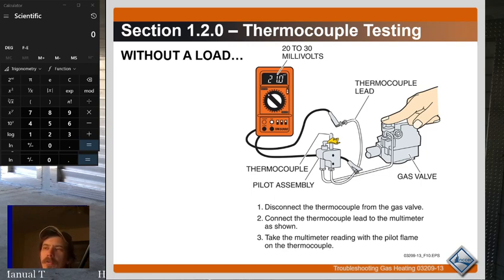And how a thermocouple works is it's a bimetal, two dissimilar metals inside a rod, right? And when it's heated up by the flame, those two dissimilar metals produce a voltage, all right? A millivolt voltage through it, and that is what holds the gas valve open.